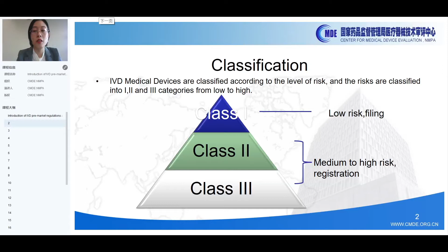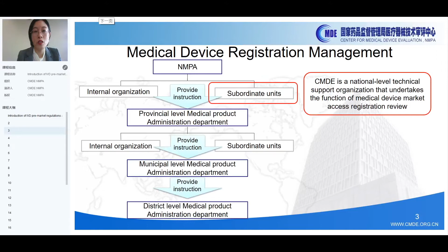Based on the classification of product, the supervision of domestic products is managed by national, provincial, and municipal level regulatory administrations. CMDE is a national-level technical support organization that undertakes the function of medical device market access registration review. All imported products are supervised by NMPA, and the CMDE conducts filing and registration review. The main responsibilities of CMDE include to conduct the acceptance and technical review of registration application of domestic Class 3 medical devices and imported medical devices, such as filing of imported Class 1 medical device. To participate in the drafting of relevant laws, regulations, and normative documents related to the registration and administration of medical devices, and other work involving research, guidance, and so on.